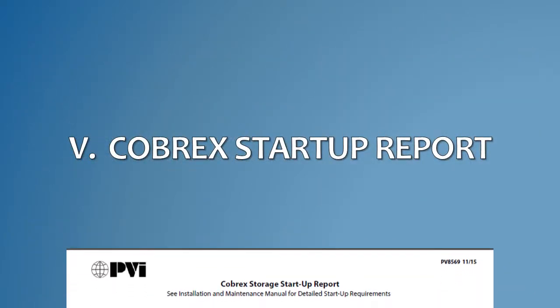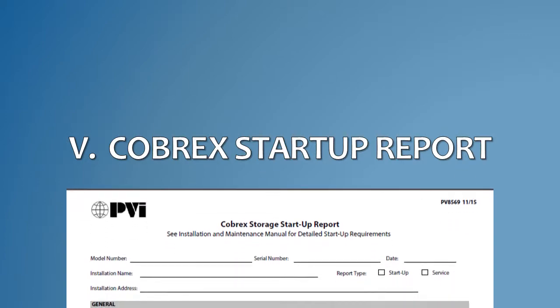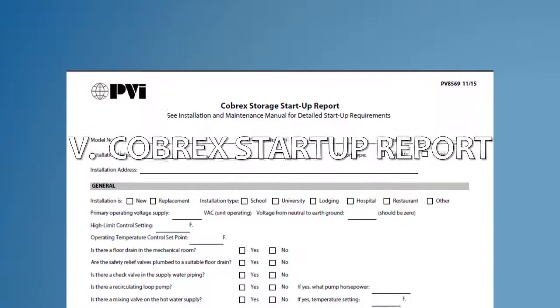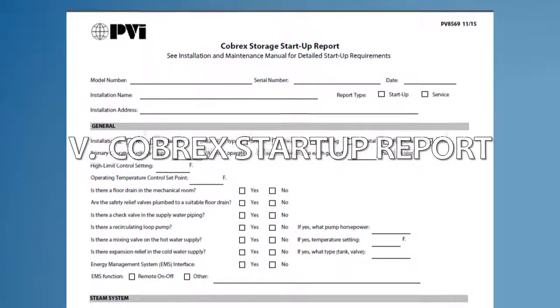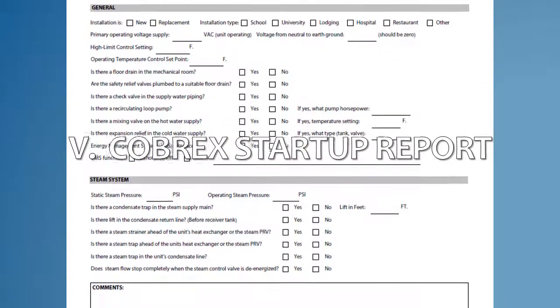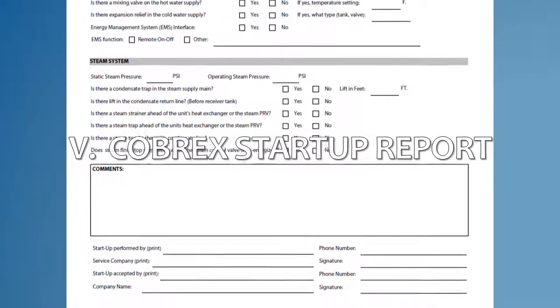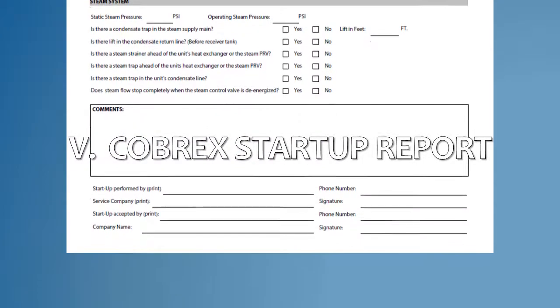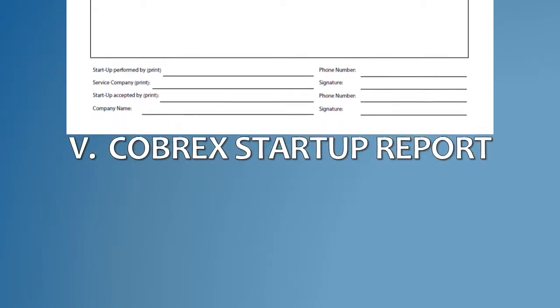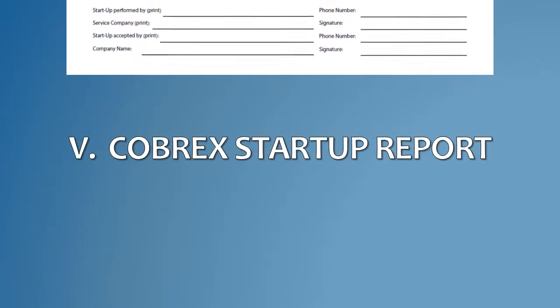The startup report furnished with this water heater must be completed and sent to the manufacturer to register the installation address and the start date of the product warranty. The information on the startup report is required. All voltages, pressures, and temperature parameters must conform to the manufacturer's specifications. Failure to ensure and document that the equipment is operating in a safe and reliable manner may cause property damage, personal injury, or death.